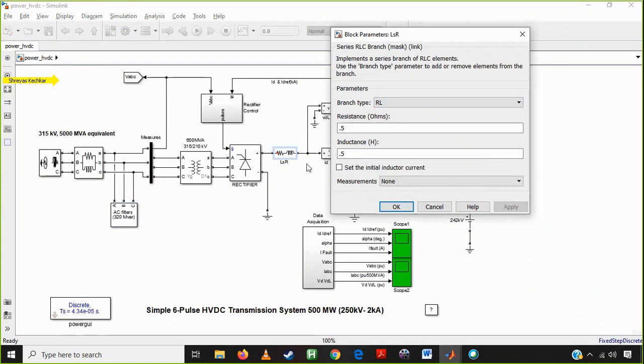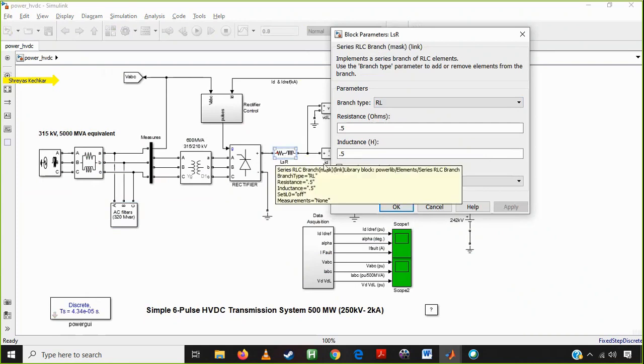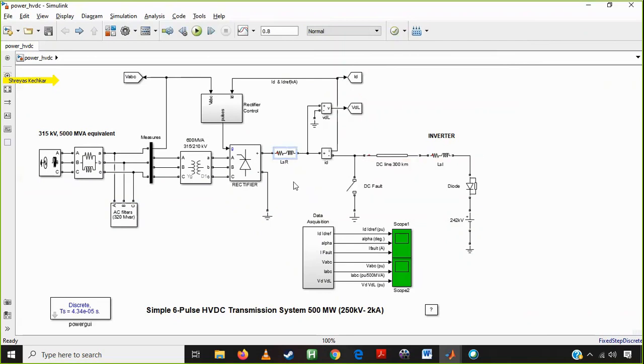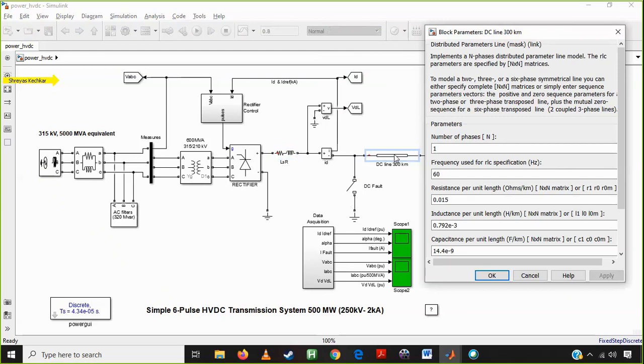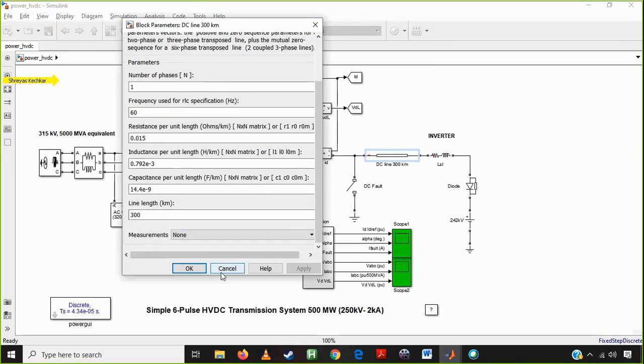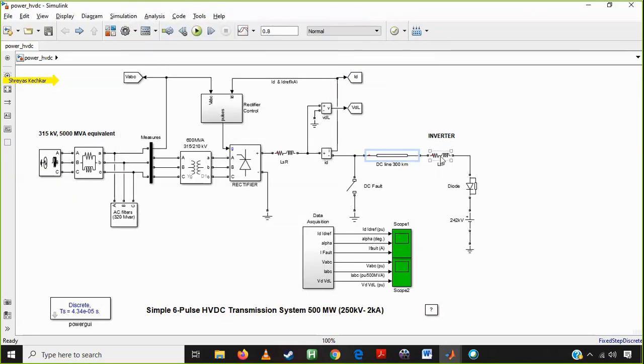The output of the rectifier has pulsation, and the smoothing inductor smooths that. A second function of the smoothing inductor is that when there is a DC fault, it limits that fault current. So there are two functions: reducing pulsation and limiting fault current. This is a DC line of 300 km — it is a long DC line. There is a 60 Hz system and 300 km on both sides. On the other end, 300 km, is the inverter.